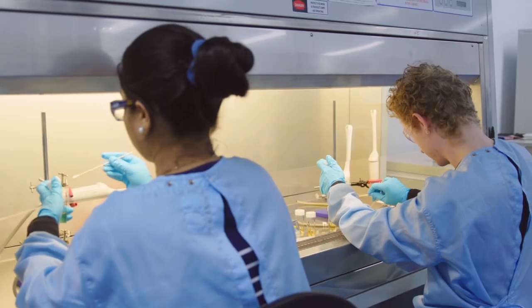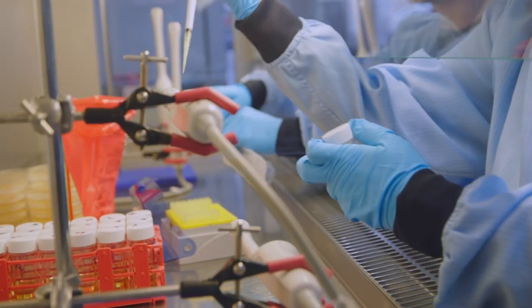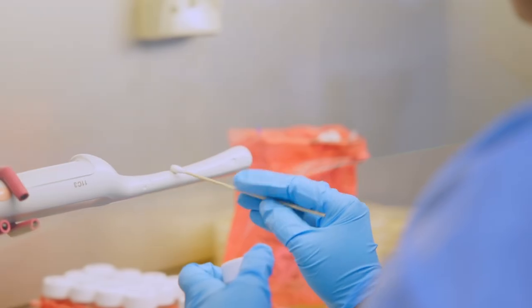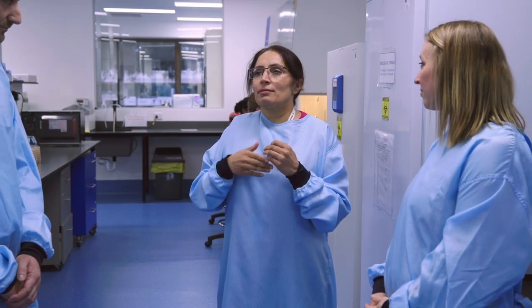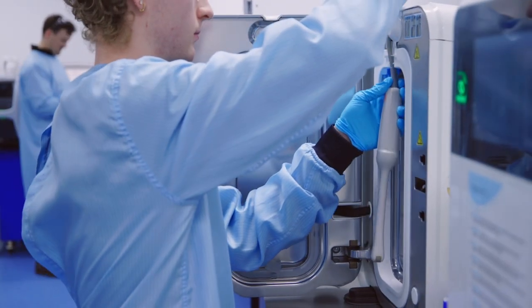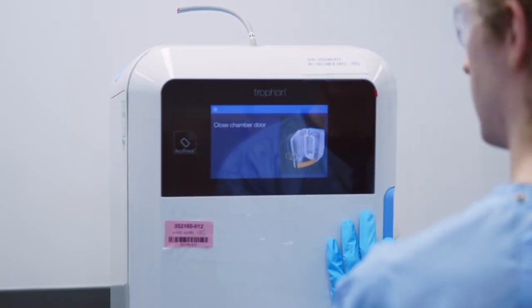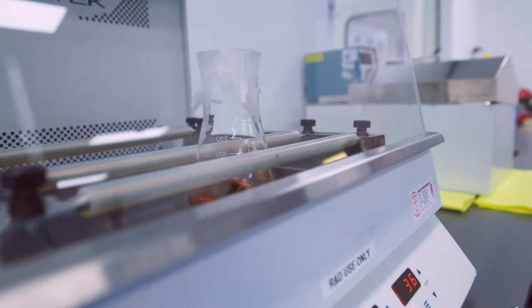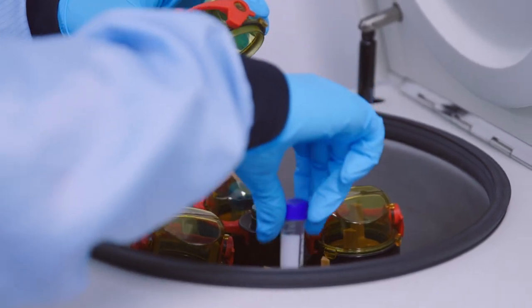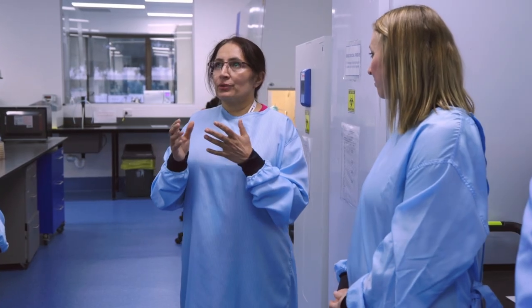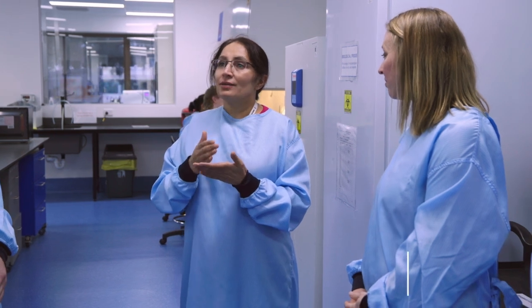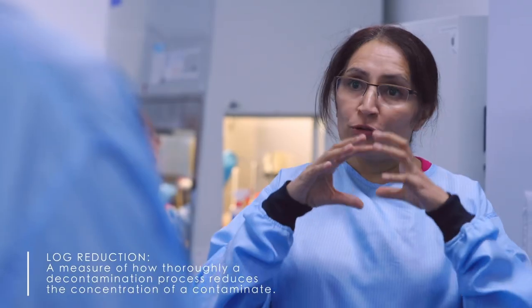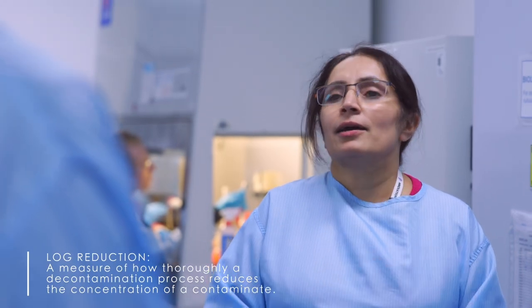Are you using real pathogens in here, or is it substitute test soils? How do you do that? That's a good question. What the process is, like you can see in the background, the real probes are actually contaminated, inoculated at multiple locations using a real pathogen. Probes are then reprocessed through the Trophon. After the reprocessing, we take the probes back and try to extract the residual bioburden. As per the regulatory requirements, we need to achieve a 6 log reduction in the bioburden on the total probe area to achieve that high-level disinfection.